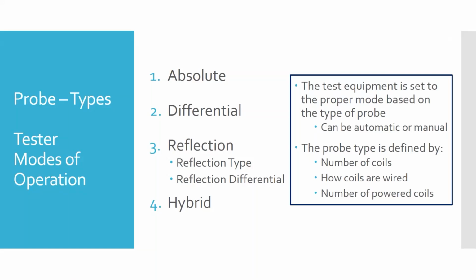So the first type of coil we'll talk about are what are called absolute probes. The second type we have are called differential. The third are reflection, and you can see there's just a standard reflection, then there's a reflection differential, which is kind of a hybrid probe. You can have probes where there's combinations of any 2 or even all 3 types of coils in them. So you have to set your equipment, your tester has to be told, or newer ones can actually auto-sense what type of coils or probes you're using.